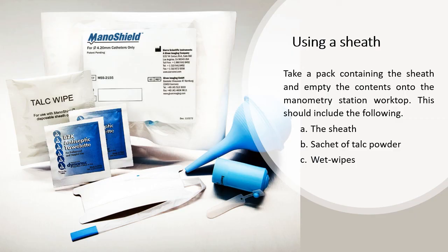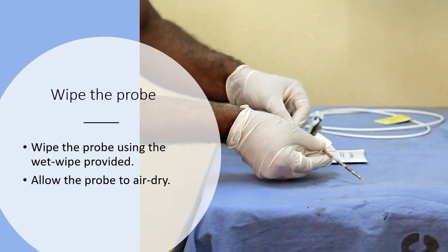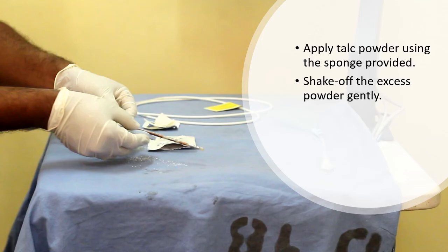Take a pack containing the sheath and empty the contents onto the manometry station worktop. This should include the following: the sheath, a sachet of talc powder, and wet wipes. Wipe the probe using the wet wipe provided. Then allow the probe to air dry. Apply talc powder using the sponge provided. Then shake off the excess powder gently.